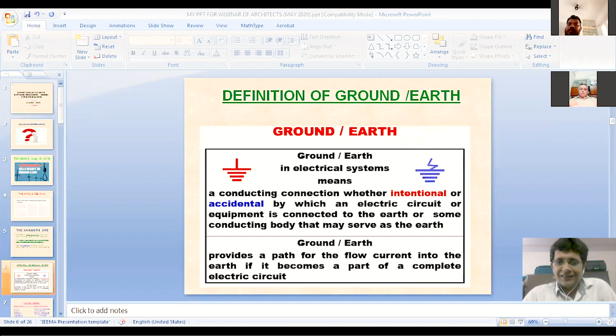I have a dream to make my India free of accidents caused by poor earthing. I'm working for that. What is ground? When you say ground, it's an automatic process - you talk about motherland. When you deliberately connect your rod to motherland, it is grounded. Even if you are not connecting any metallic part or electrode to motherland, it is still grounding. The difference is that one is an intentional grounded system, the second is an accidental grounded system. When it becomes accidental, we have to give a path to the fault current back to the source so that we can remain safe.